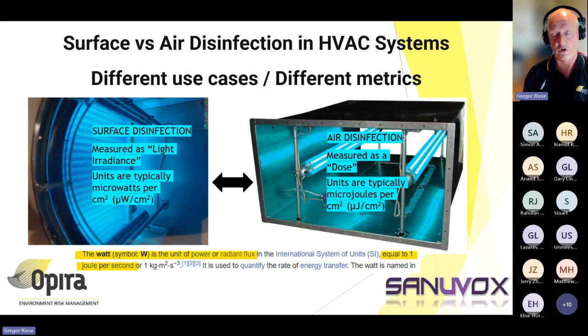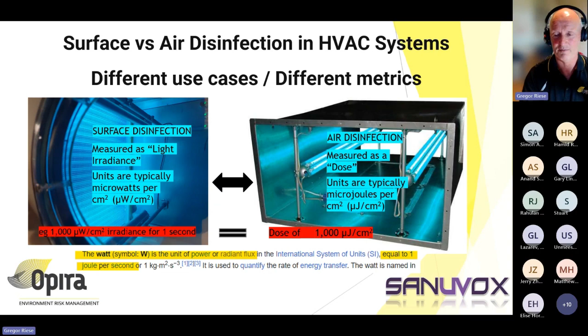That's the industry standard. And the alternative there is air disinfection, which is measured as a dose, so it's in joules, and that is in microjoules per centimetre squared. When the industry sizes these up, these are the units we use. And of course, you can convert from watts to joules. 1 watt times a second is equivalent to 1 joule. So if you've got a little bacteria sitting there on your coil surface being irradiated with 1,000 microwatts for a second, it's been dosed with 1,000 microjoules. I know our little bug isn't a centimetre squared, but you get the idea, and that's the back of the envelope kind of conversion you can do, because very often you'll have customers asking for air disinfection on a coil installation, and we'll be circling back on that theme as well.